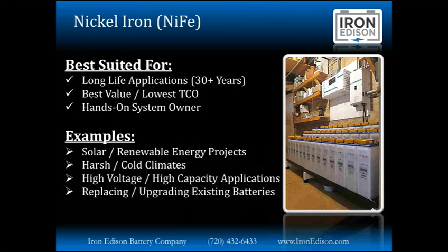So to summarize, nickel iron batteries have a great long life in applications they're used in. The best value, or the lowest total cost of ownership of any battery chemistry you're going to find out there. Nickel iron is great for hands-on system owners because there is a little bit of maintenance required. Again, not nearly the maintenance regimen that you need for lead acid batteries, but you do have to maintain them just a little bit.